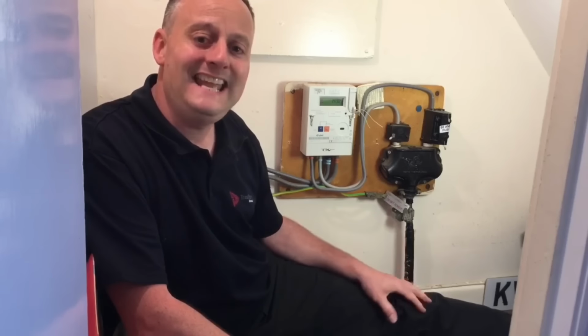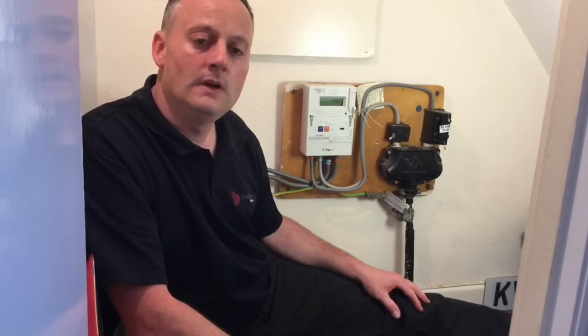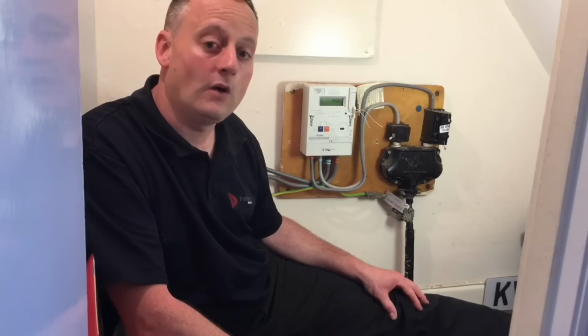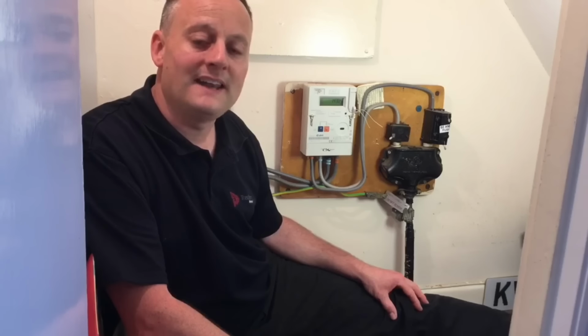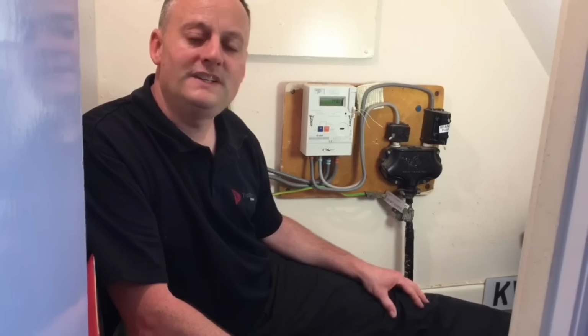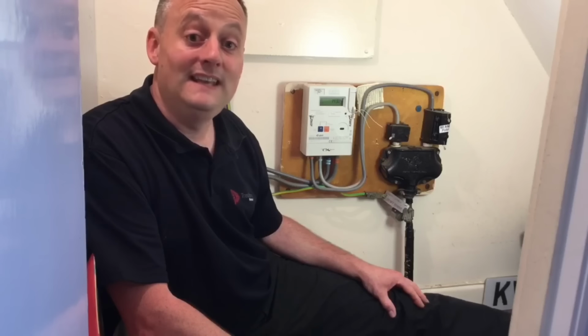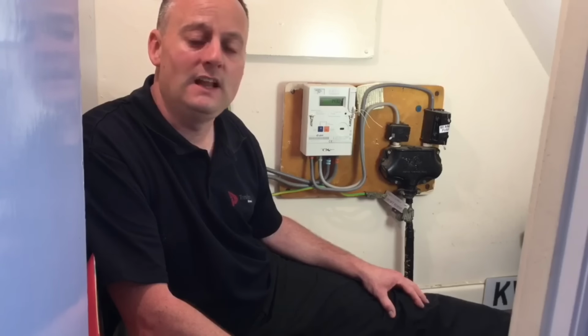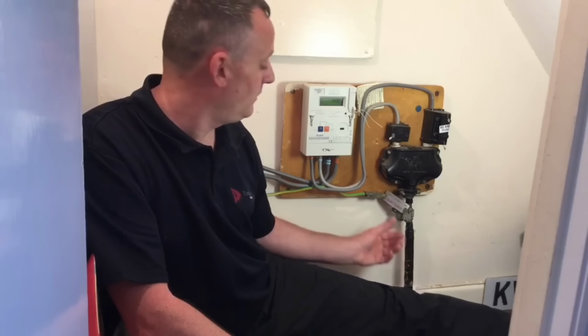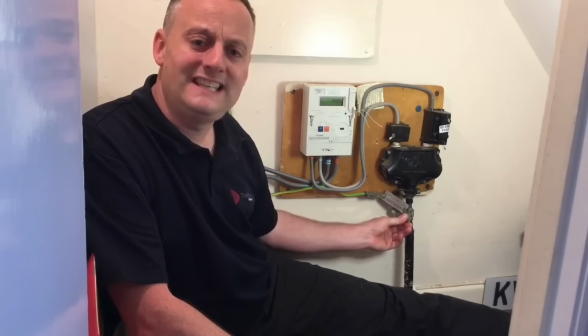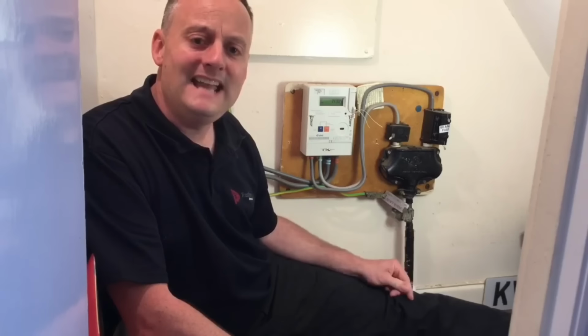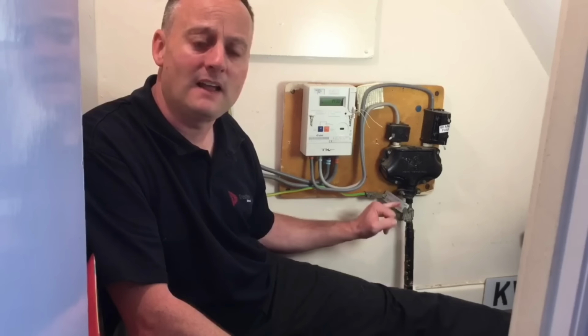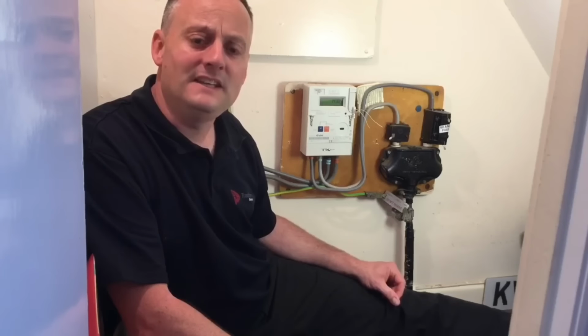So we're looking at a TN, a terra neutral, and then S for separate. In other words, the supply authorities will bring in a line conductor, a neutral conductor, and a separate earthing conductor into the installation. The two common materials used for this separate earthing conductor coming into this installation are either lead of the sheath of the cable or steel of the sheath of the cable. In this instance, we're coming off with a connection to a steel sheath cable. If it was a lead sheath cable, care must be taken to check the clamp around the lead is correct.